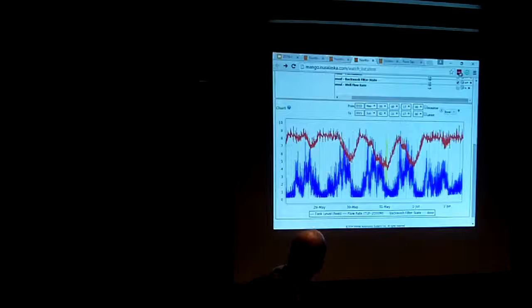But relative to when there's very little flow, it gives me a good idea of what's going on in the plant. So I can see our tank level dropping and usage going way up. We can see the backwash cycles happening, and it started dropping before the backwash cycling began. It was working fine before, and it recovered after the backwash cycle, so I can tell there isn't a problem there.